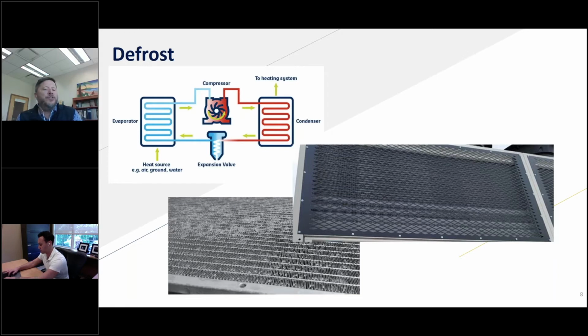Some frosting of the coil in and of itself doesn't stop the equipment from running; the machine's going to keep running. But as we build more frost and it accumulates on the coil, it reduces our ability to transfer energy or move heat. The more frost we have on the coil, the harder it is to transfer the heat from the air to the refrigerant. Because of that, we see the efficiency of the machine degrade, and at some point it's going to get to where we don't want to keep that ice on there.